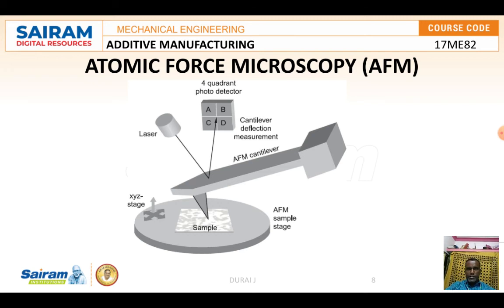In addition to angstrom level positioning and feedback loop control, there are two main components in atomic force microscopy: deflection and force measurement. For probe deflection, traditionally most atomic force microscopes use a laser beam deflection system, where the laser is reflected from the back of the reflective cantilever onto a position sensitive detector.